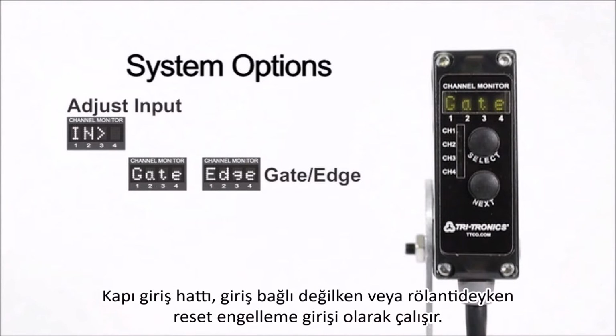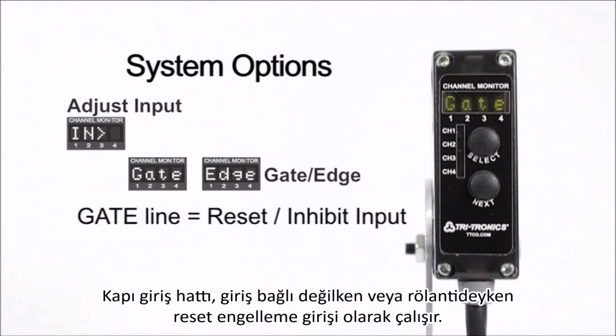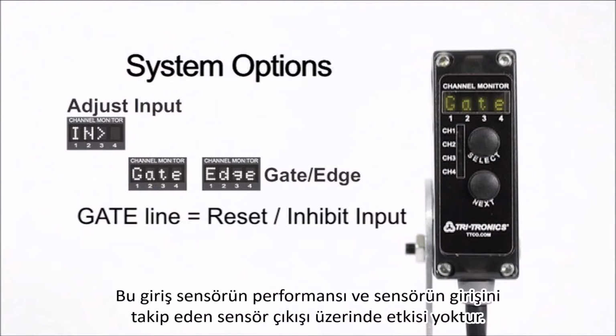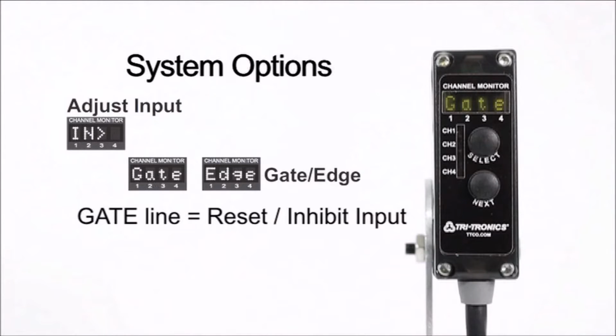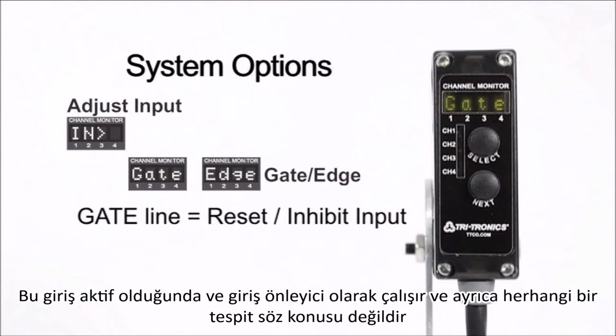In gate mode, the gate input line acts as a reset inhibit input. When this input is not connected or is in the idle state, this input has no effect on sensor performance, and sensor output follows sensor input. When this input is active, it acts as an input inhibit, and no further detections will occur.